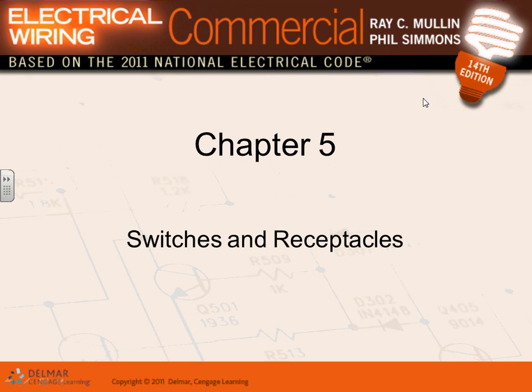Any questions about what we did yesterday, guys, talking about circuits? We mentioned, Karen, yesterday that we're going to be circuiting 17 lighting fixtures on a 20 amp, 120 volt circuit, and we're going to be doing 6 receptacles. You can switch it to 7 or 8 receptacles on one circuit, but we're going to stick with 6 receptacles in one circuit if we can. That's the circuiting mechanism that we're going to use. An extra receptacle in one corner added to make it 7 wouldn't be a big deal.